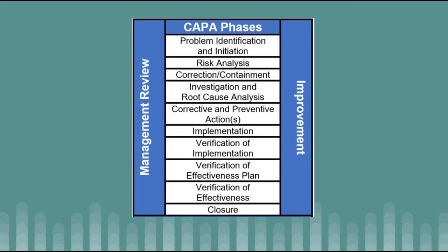In other words, as shown in the image, in order to fulfill the corrective and preventive action, different phases have to be met. For the first phase, shown in that middle section of the image in white, it's to document the issue by explaining who, what, when, where, why, and how many. For that second phase down, it's based off of patient user compliance risks. Low risk and high risk issues should be documented to see which risks are most urgent.